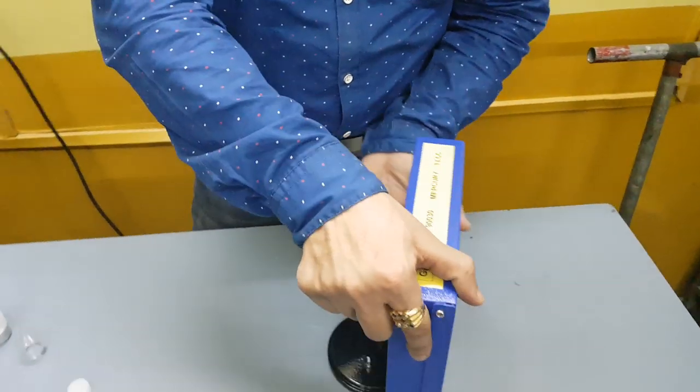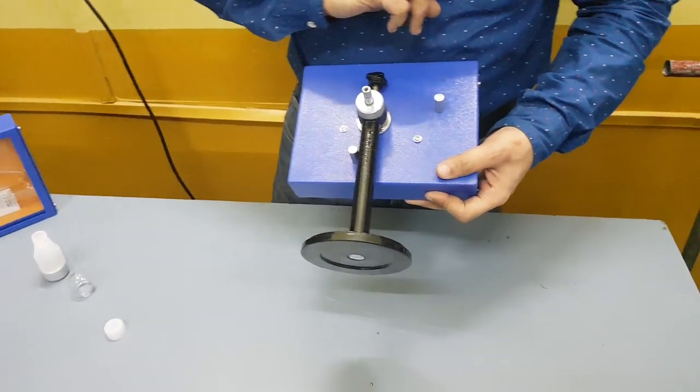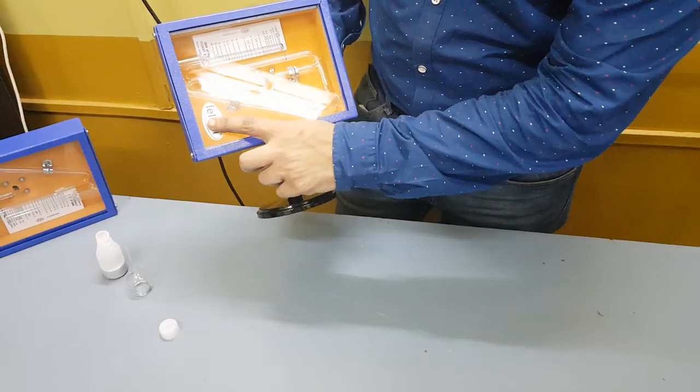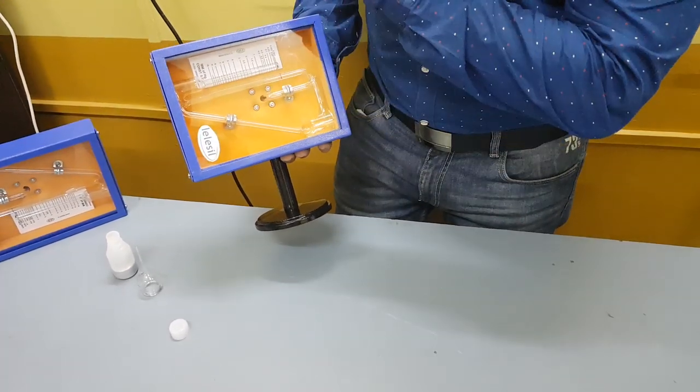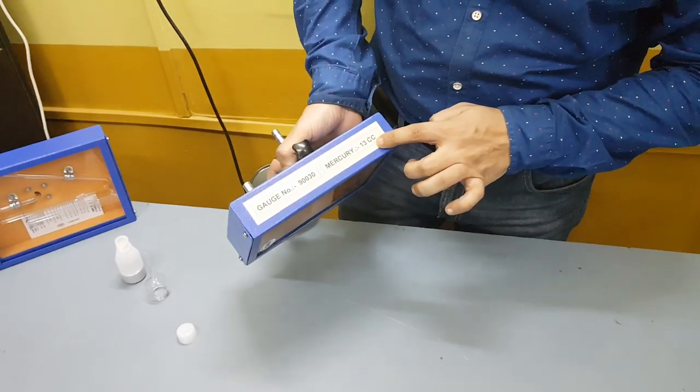Now to start with, there are two locking bolts provided at the back and a locking nut. When you have to fill mercury, you have to ensure that you are parallel to the logo, the scale is at the top. Gradually tilt it in such a way that the gauge number is seen at the top.